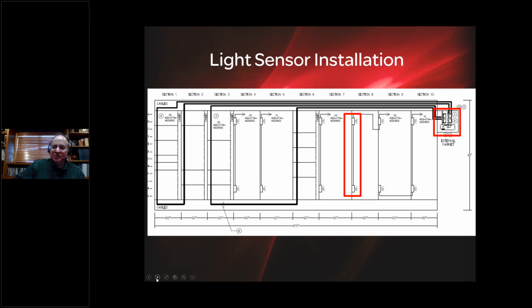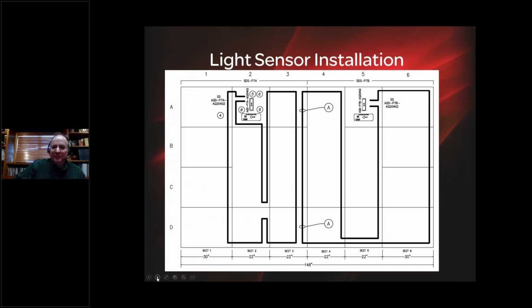But the actual placement of both the point light sensors and the fiber light sensors in this equipment is a result of empirical testing that has been done in high power test labs to verify, under all arc flash conditions, that the light sensors would properly assert. Here is another example of a light sensor installation, this time in a variable frequency drive and MCC combination. And you can see again, in this case, we had room, since this was a new installation, to install the annunciation panel and the arc flash relays in the MCC.